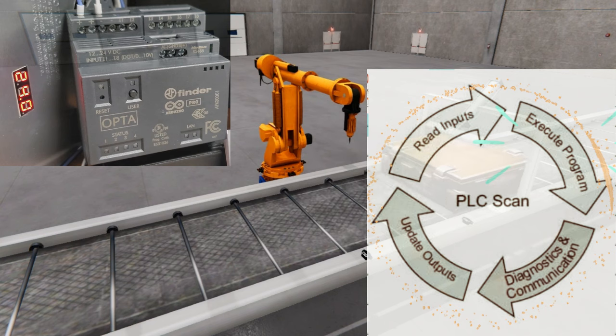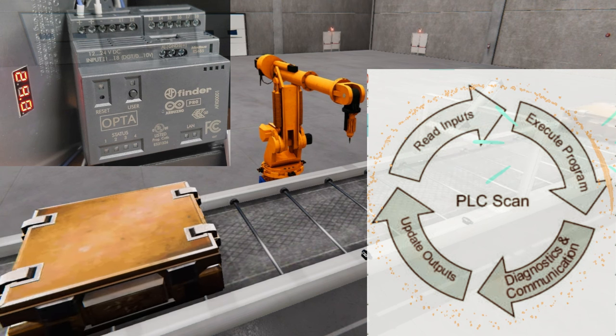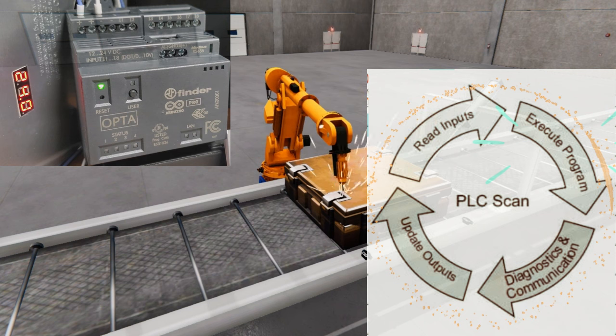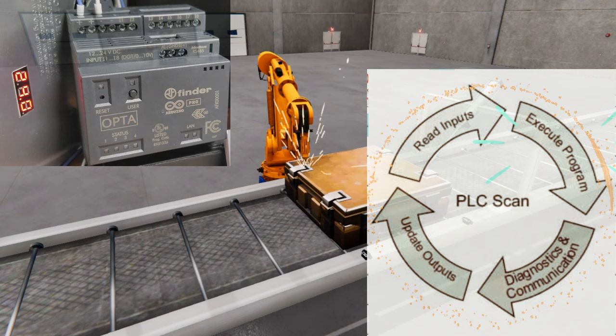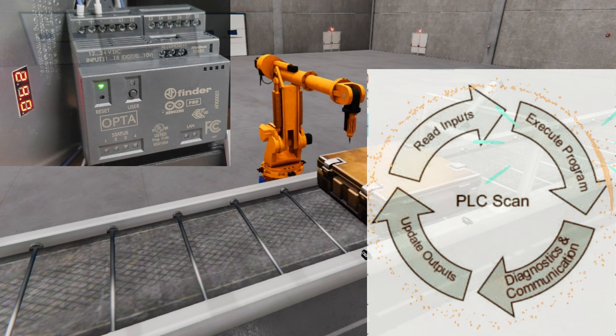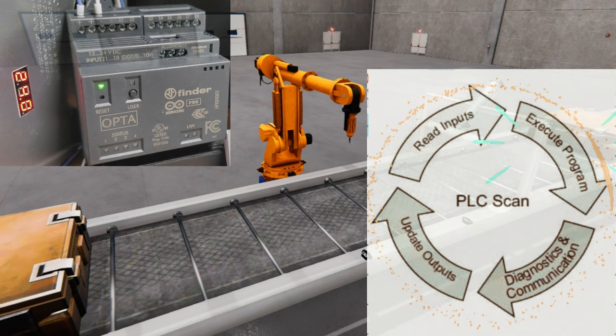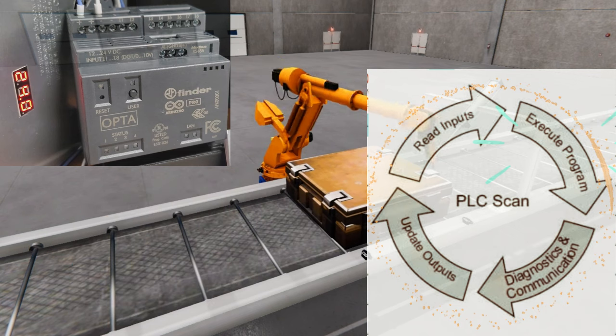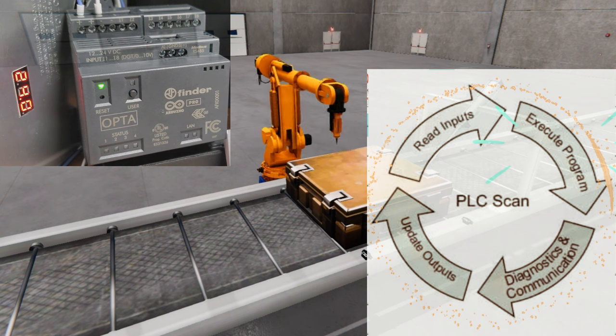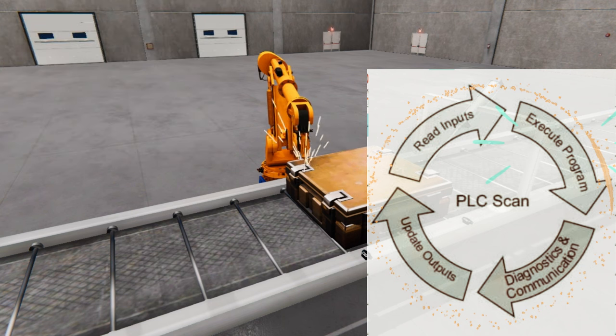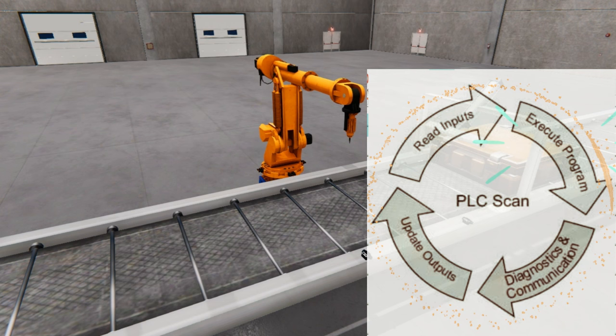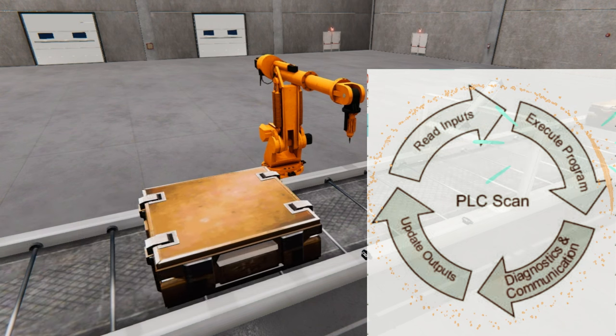The operation of a PLC revolves around four fundamental stages: scanning of inputs, executing programs, diagnostics and communication, and updating of outputs. Initially, in the input scan stage, the PLC assesses the condition of the inputs. During the following program scan stage, it puts the previously written control program in its memory into action. Diagnostics will ensure that PLC memory and devices are working correctly. Communication will be handled to other devices or within the controller itself. Lastly, at the output scan stage, it updates the output's conditions depending on the operational inputs and the program embedded in its memory. Scanning happens cyclically, meaning this operation happens several times per second.